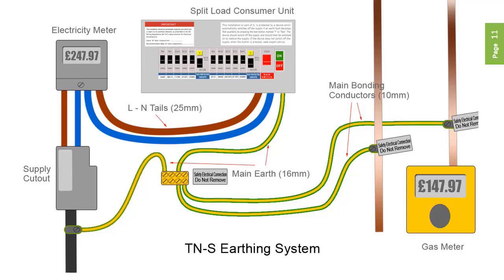Care should be taken that the earth conductor is the correct size and is securely fixed. If not, the supply authorities should be contacted, as this is their responsibility and property. A TNS system has a maximum earth fault loop impedance, or ZE, of 0.8 ohms.